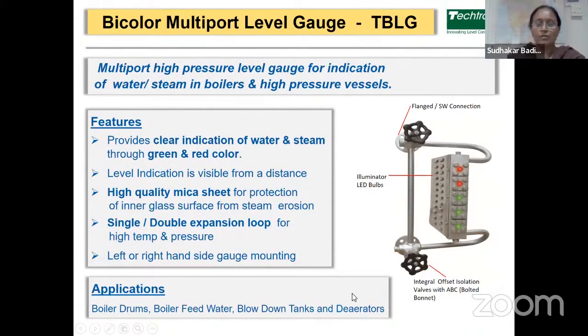The next one is a bicolor multi-port level gauge. This is a multi-port high pressure level gauge for indication of water and steam in boilers and high pressure vessels. Basically, it gives you the clear indication of water and steam in green and red color. That is, green color shows the level of the water, and red color shows the level of the steam. The indication can be seen from a distance. It is visible from a distance. It uses high quality mica sheets for protection of inner glass surface from steam erosion. Then single and double expansion loops are available for high temperature applications.